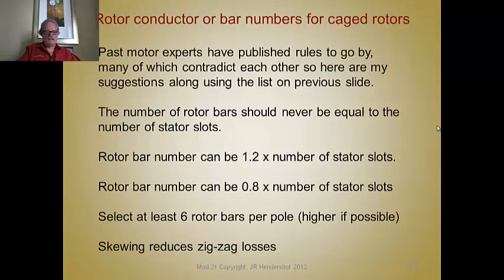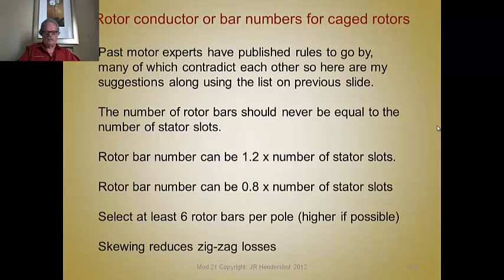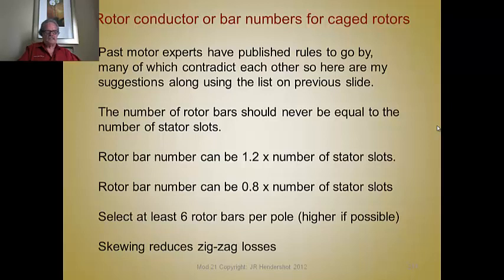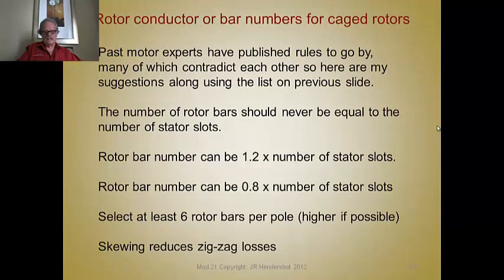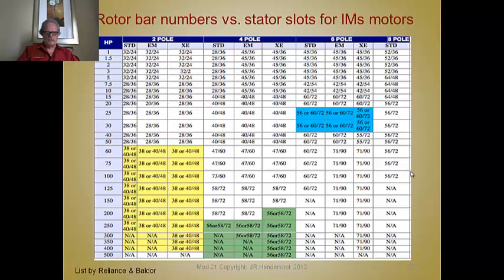A good rule of thumb is five to seven rotor bars for each pole at minimum, and higher if possible. In larger machines you want to go up to seven, eight, or nine rotor bars per pole. It's a tricky balance to get the width of the bar and the width of the tooth optimized so there's no space wasted. With the tooth we have to deal with low-speed peak torque flux densities — you don't want to reach saturation. And with the bar, at those same peak torques you'll be at maximum current, since the torque-producing current flows in the rotor bars, so current densities must be at acceptable values.